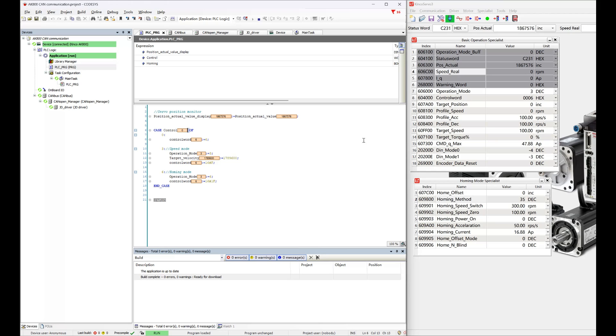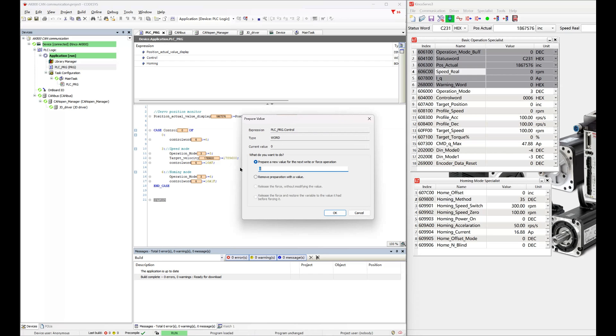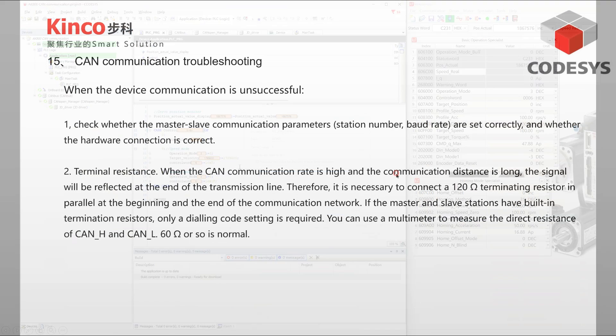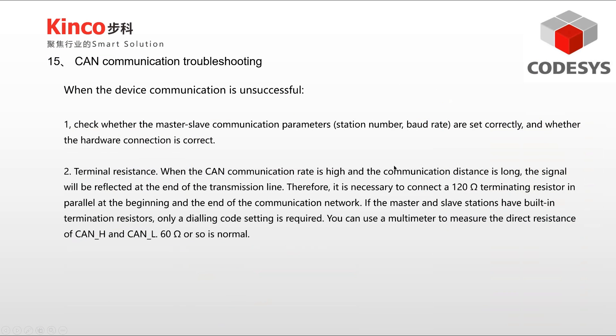This is the control case for servo CANOPEN. In actual operation, you can set it according to the process of the equipment. Now we are going to talk about common CANOPEN error troubleshooting. When device communication fails, you can check the following tips. First, check whether the master and slave communication parameters such as station number and baud rate are set correctly, and whether the hardware connection is correct.